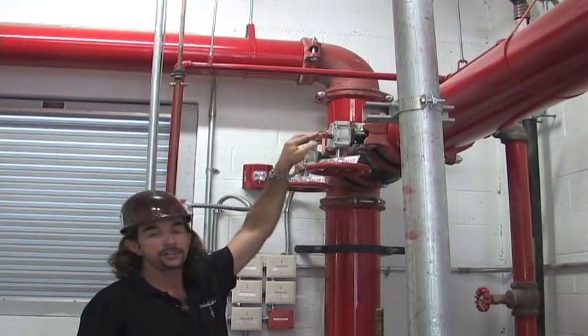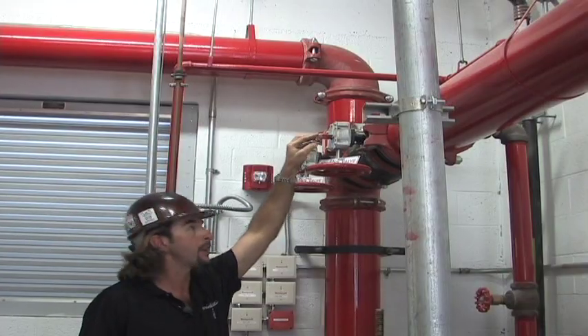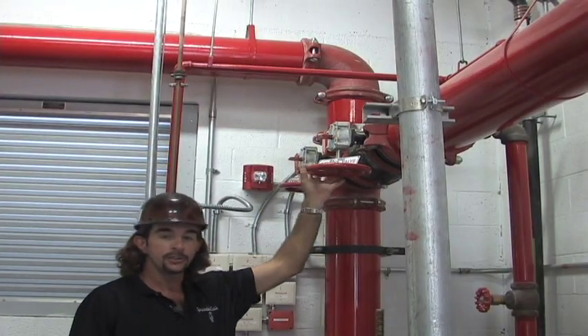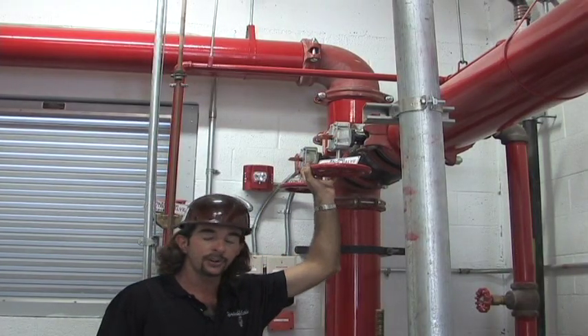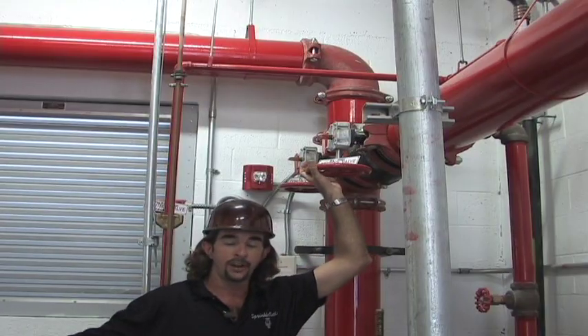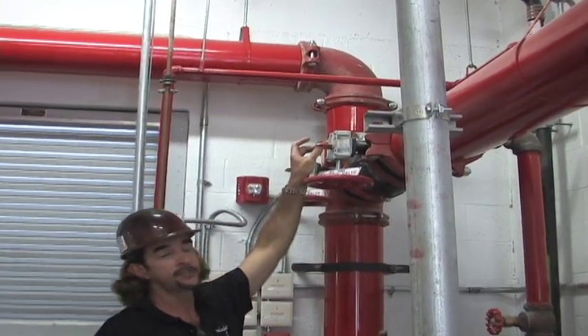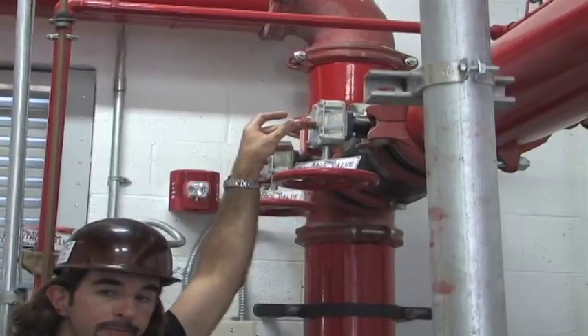These valves also have a tamper inside of them, but they work off the inside. As soon as you start to close this thing after 5 turns, you have a trouble going back to the fire alarm panel saying the bypass valve number 2 is closed. As far as our maintenance goes on the electric fire pump, it's very easy.